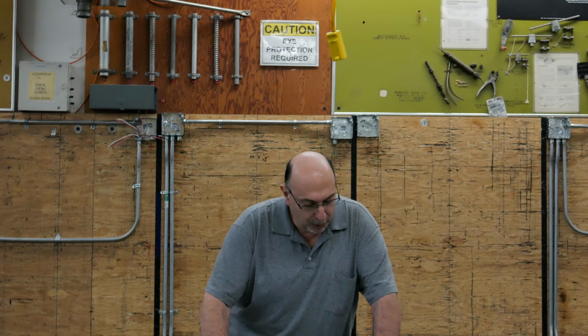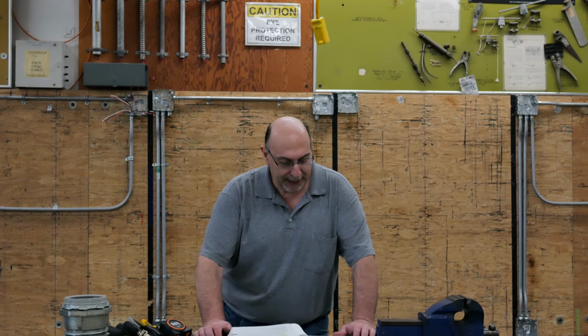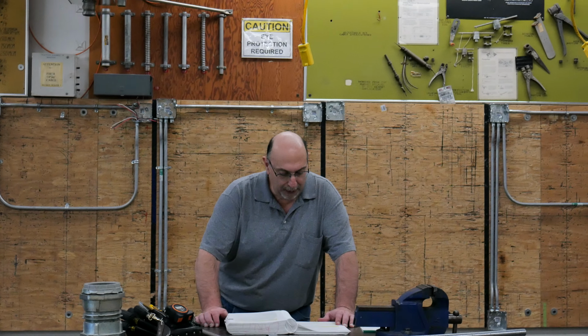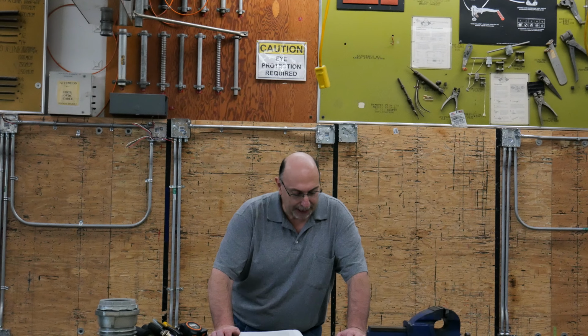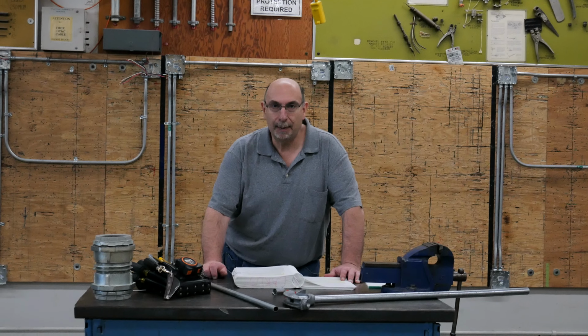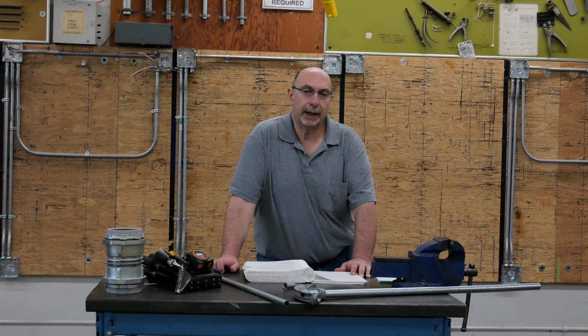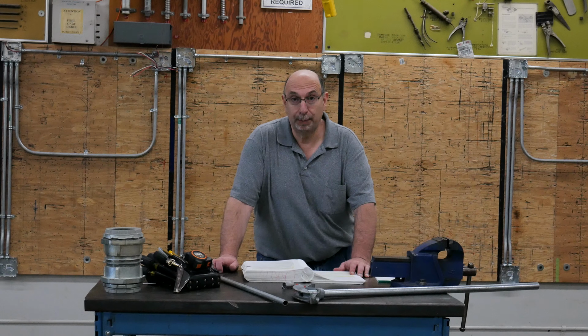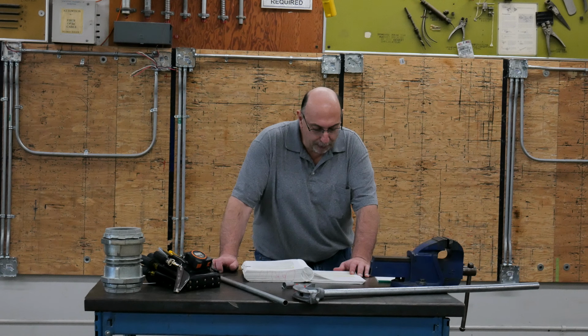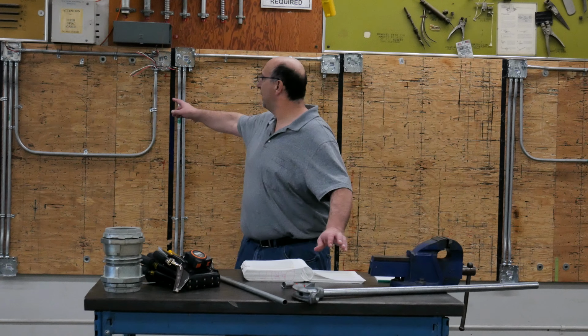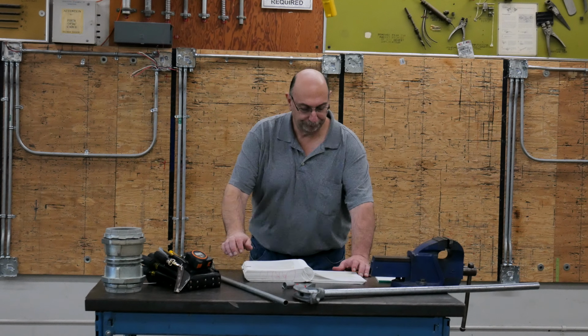Now, this is a trick. The next subrule is a trick. Subrule 2, where insulated conductors are number 8 AWG or larger, copper or aluminum, such protection shall consist of. And the trick there is, they like to trick you on the wording of that number 8. So the little trick is, where the conductor is larger than number 10, i.e. number 8, you must provide some form of protection right here at that connector.